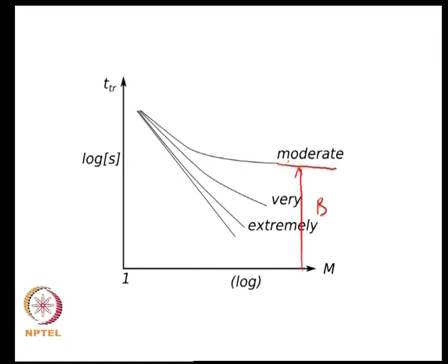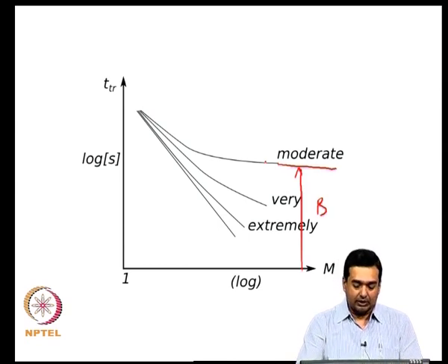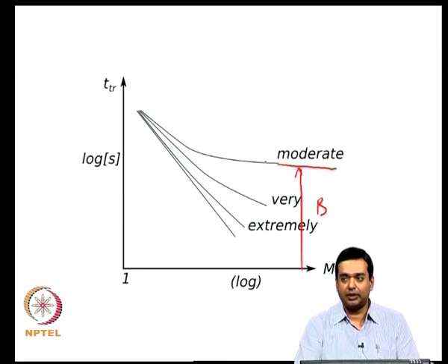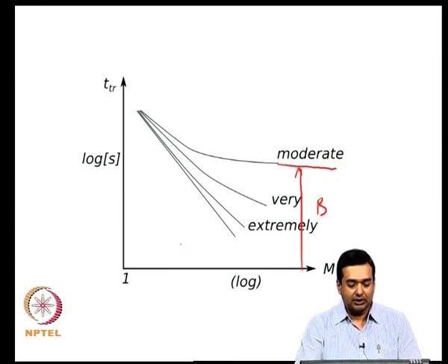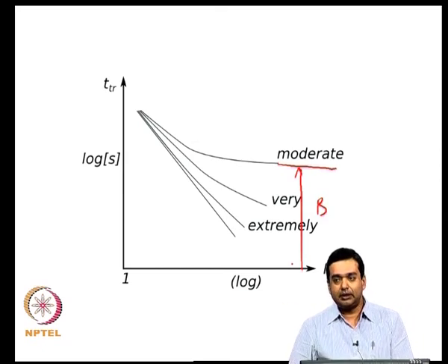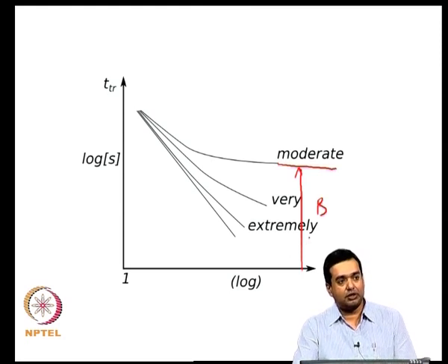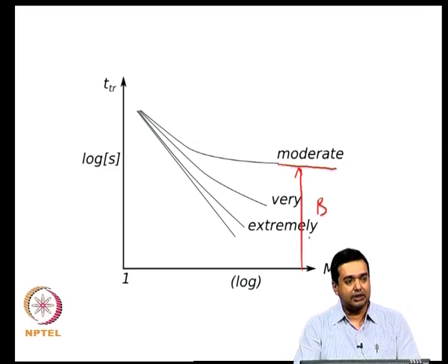Okay. So, this type of characteristic is useful when you have components such as motors, where your motor starting current might be large, which means that you will be operating at m which is large, but then once the motor speeds up, the current would come down. So, you can actually operate your device without causing your breaker to trip when you are starting the machine.